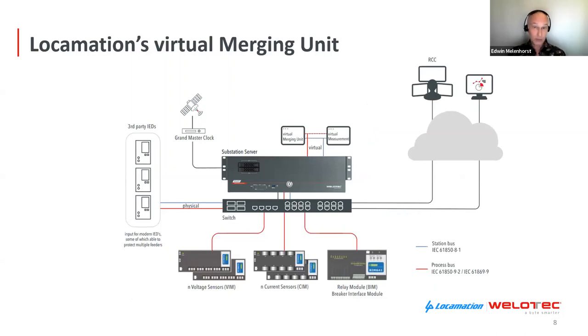The virtual merging unit is a solution built on a simple, robust sensor connected to a single software-defined merging unit, running on a commercial off-the-shelf industrial computer. The sensors do not need configuration in most cases, and the virtual merging unit can publish up to 30 sampled value streams for protection, measurement, metering, and other applications. Because the virtual merging unit is based on IEC 61850, the way to multi-vendor solutions is guaranteed.